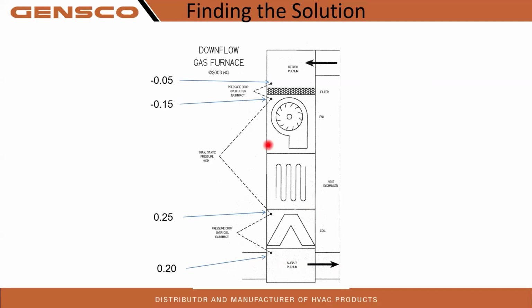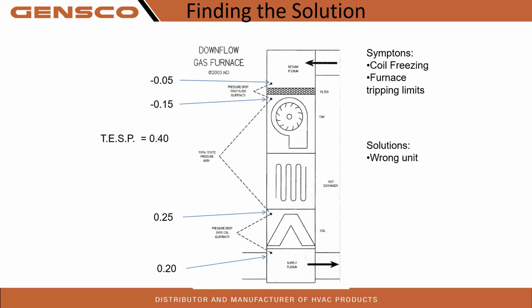So four holes in your system, checking static can tell you a lot. All right, total external static is 0.4. So we're kind of close on this one, but we have light airflow. This is kind of opposite of having restricted ductwork, right? But it'll show you the same symptoms: coil freezing, furnace tripping limits. It could be a wrong unit for your ductwork.